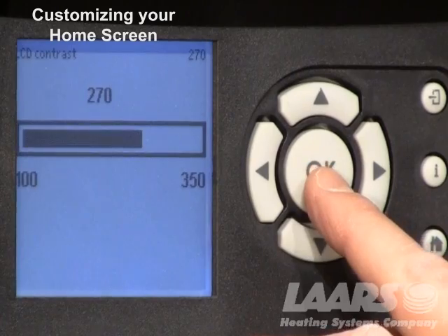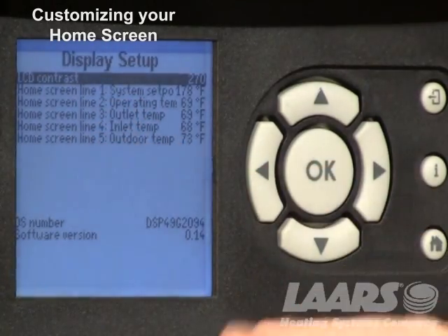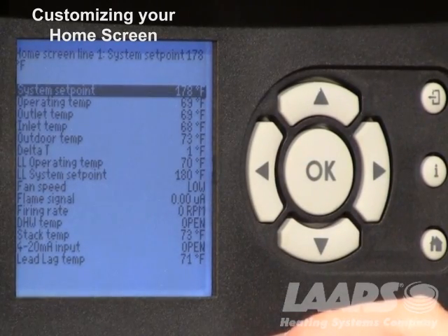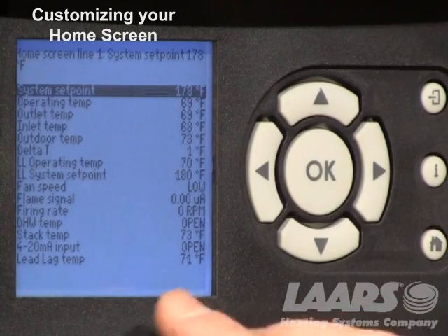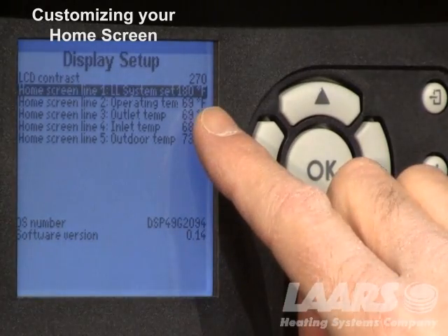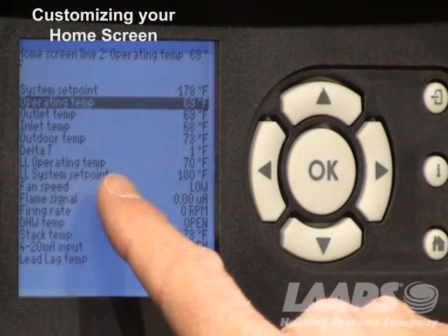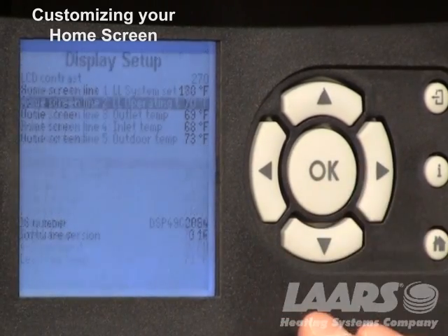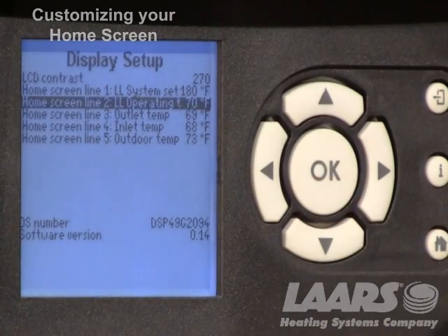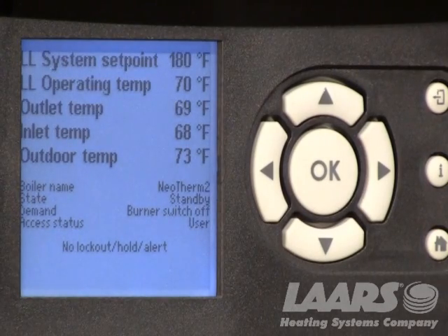Once you've chosen how dark you want the screen, press okay and it returns to the display setup screen. You have line items one through five which you can customize. Go down and choose line item one, highlight it, press okay, and these are all the options for the main screen. Since we're using a lead lag sensor, scroll down to lead lag set point, highlight it, click okay, and it will appear on the main screen. For line item two, highlight it, press okay, and choose lead lag operating temperature. If you're using an outdoor reset function, that will show your operating temperature and system set point. Click okay and go back to the home screen — you'll now see lead lag system set point and lead lag operating temperature at the top.